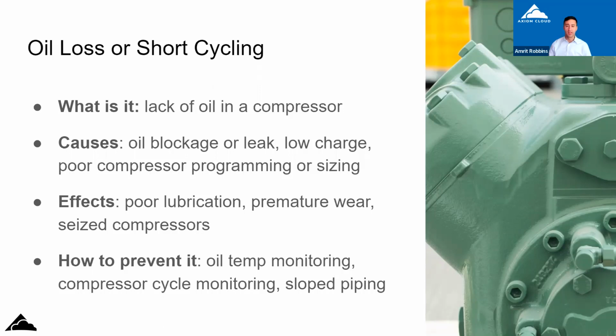Obviously, short cycling can be another major root cause of oil issues, because oil takes a few minutes to really start washing throughout the body of a compressor. And so I guess right off the bat, Trevor, how does this stack up against the other failure modes that you see in your trainings when you're talking to new technicians?